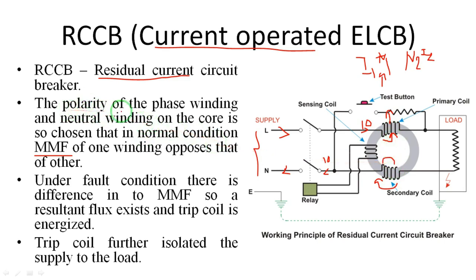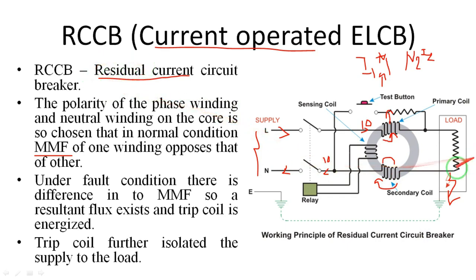The polarity of the phase winding and neutral winding on the core is chosen so that under normal conditions, the MMF — magnetomotive force — of one winding opposes that of the other. Since the same current flows through the same number of turns, the MMF values are equal but in opposite directions, so the differential flux becomes zero. However, if an earth leakage current occurs, the return current becomes reduced — for example, from 10 amperes down to 9 amperes. The number of turns remain equal but the currents differ, so the MMF values are also different.